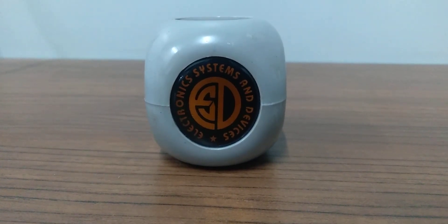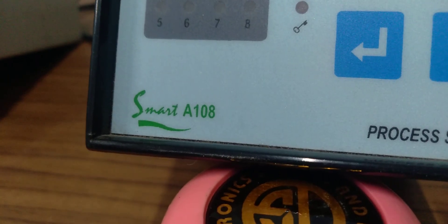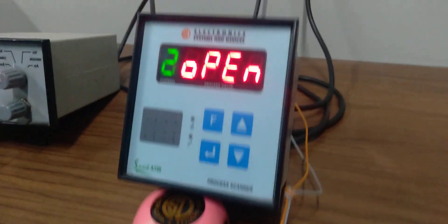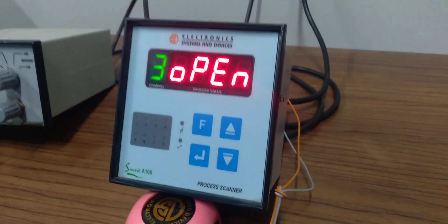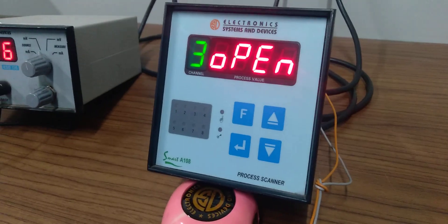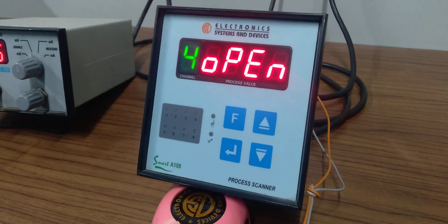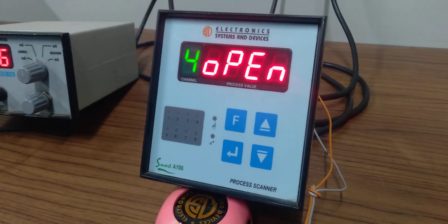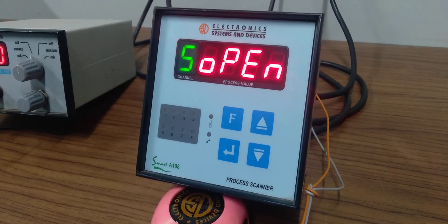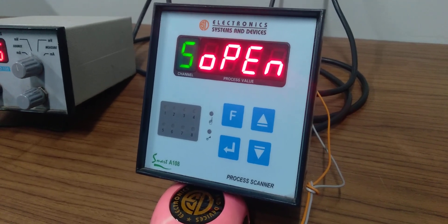Hello, welcome to product demonstration for Electronic Systems and Devices. The product we are covering today is a process scanner. The model is Smart A108, an 8-point common alarm model. Common alarm means there will be one relay output for the alarm and one for the trip. Alarm is for the lower side, trip is for the higher setpoint side.